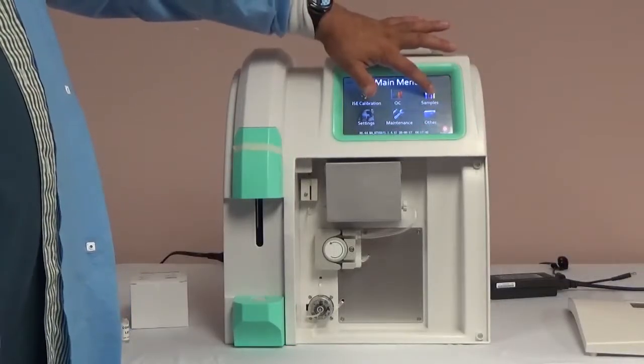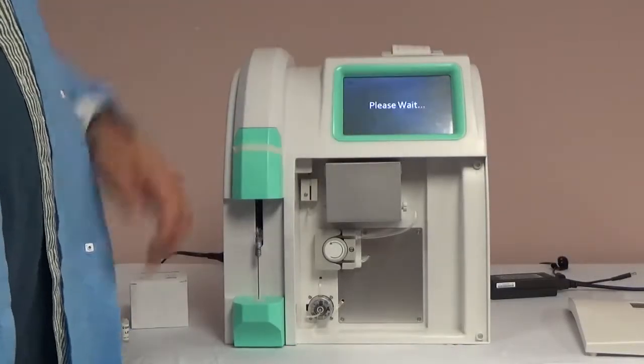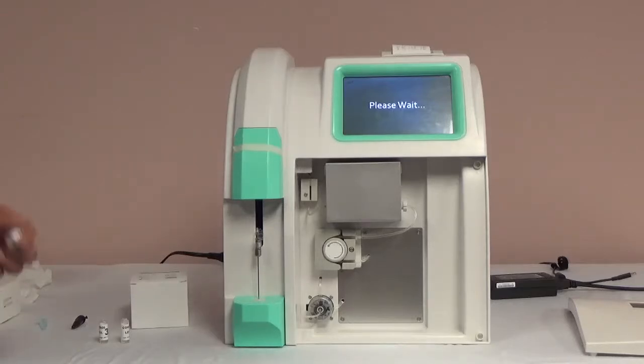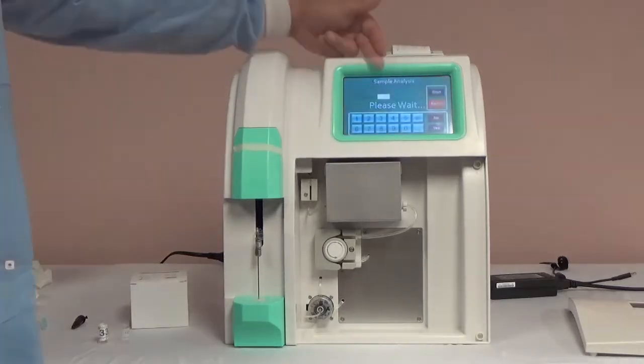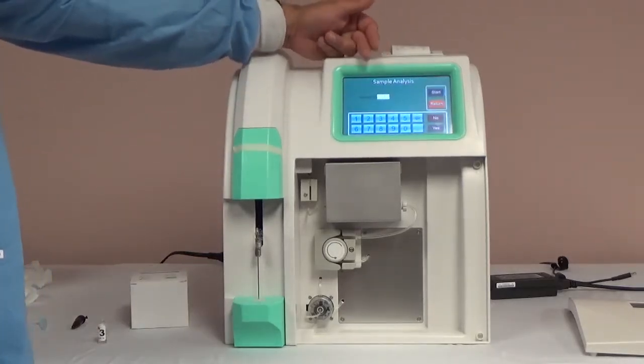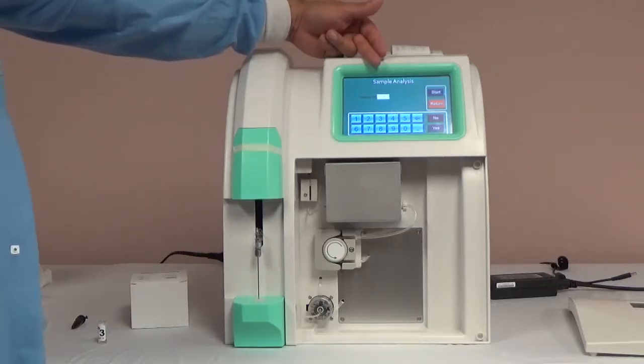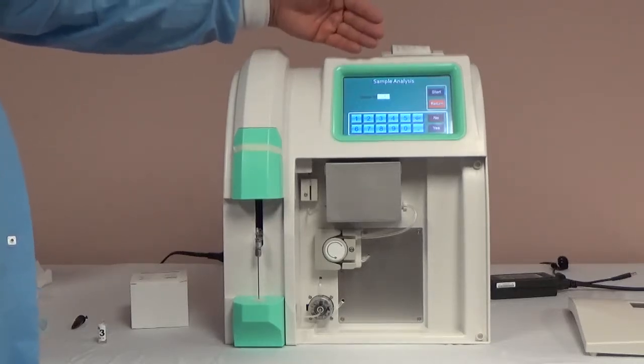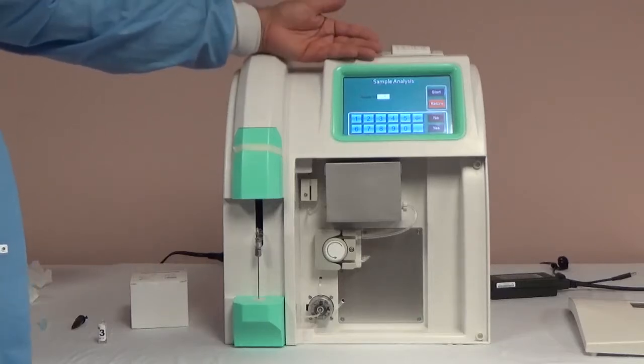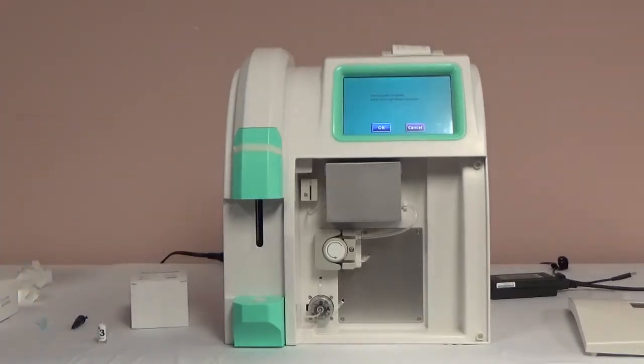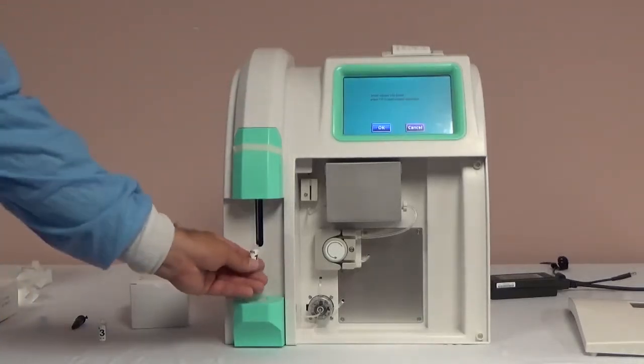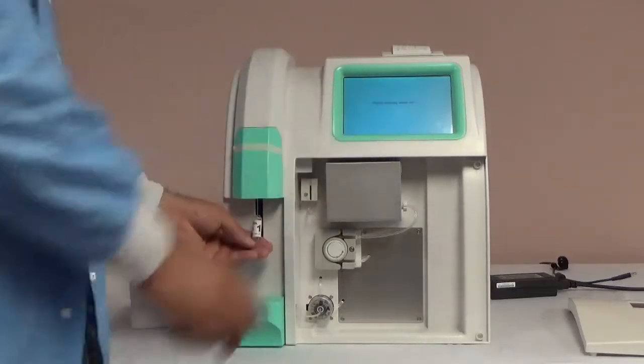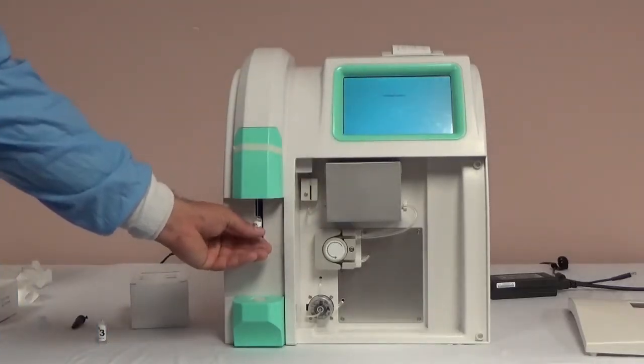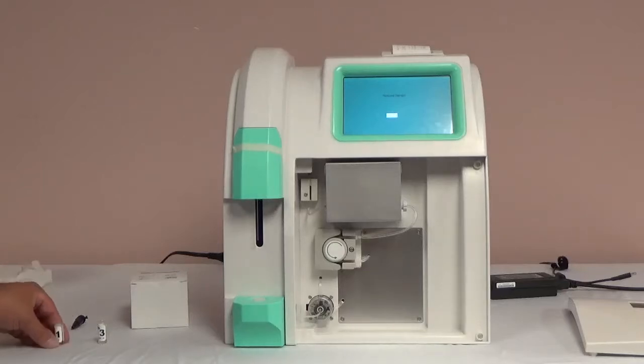To begin running samples, you will select the sample screen from the main menu. The sample process is very similar to the QC process. Once the analyzer is ready, you can enter the sample ID, a unique ID, or leave it at 1, but note it will label the samples consecutively based on the number you enter. The analyzer will ask that you insert the sample onto the probe, press OK, and remove the sample when prompted. The analyzer will process the sample and will show you the results on the screen as well as print them out. Repeat the process of sampling when ready.